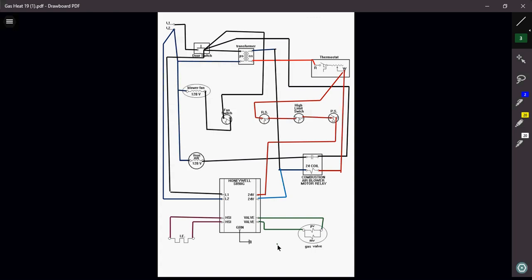So there are different variations of units out there. You just kind of have to look at the wiring diagram and look at the wires to see what actually brings the blower on, what timing, and what brings on my hot surface igniter. The same thing applies to your hot surface igniter systems. Usually these types of furnaces have a pre-purge setting. Pre-purge simply allows the vent motor to run for a certain amount of time before it moves on to the next sequence of ignition.